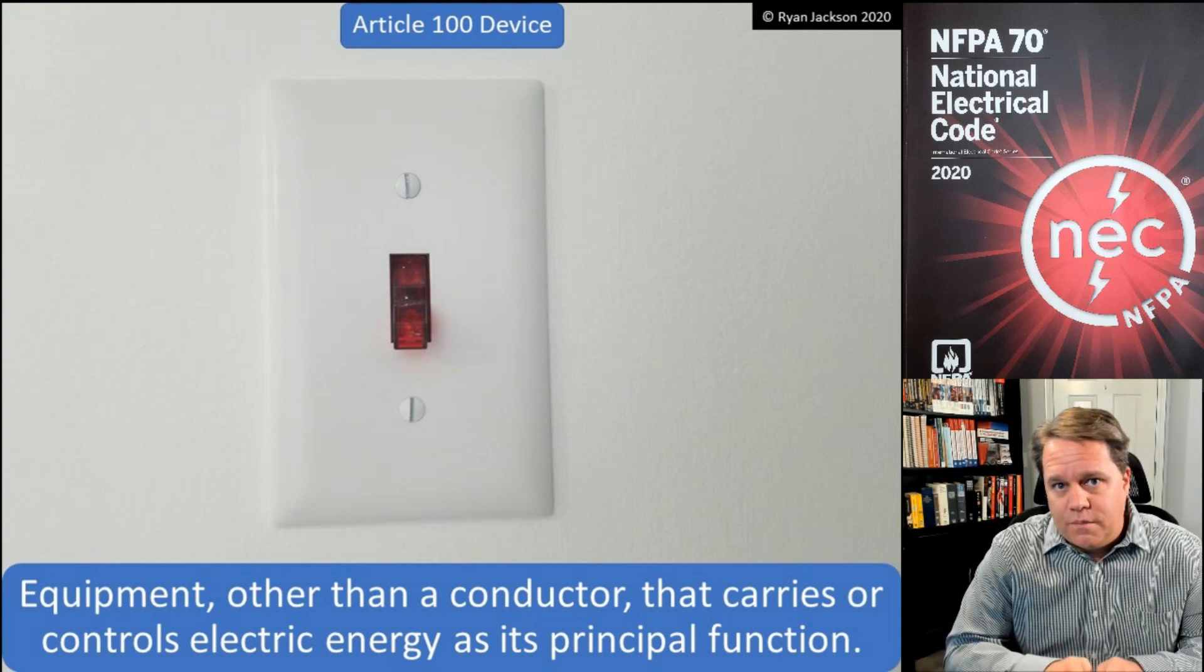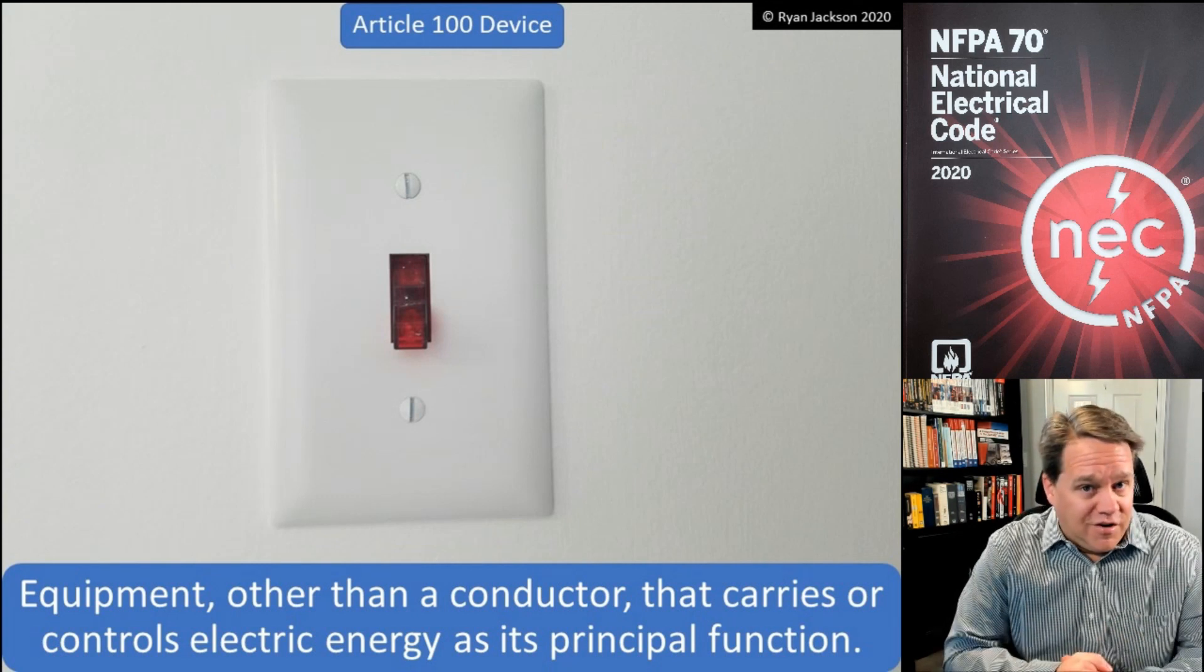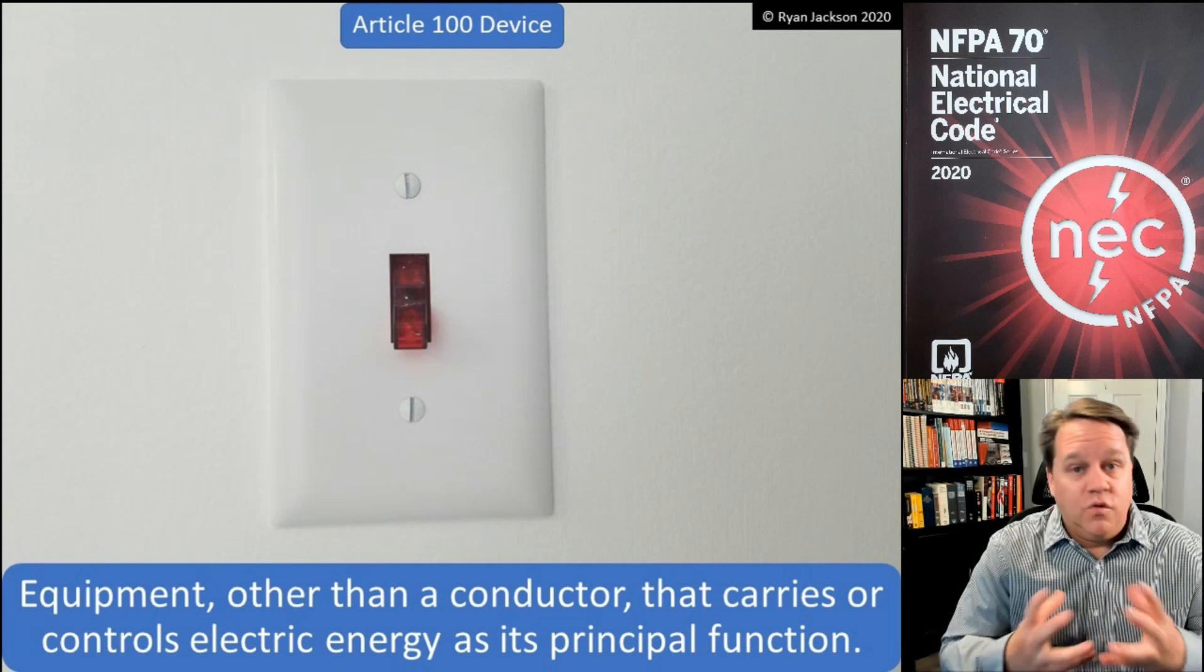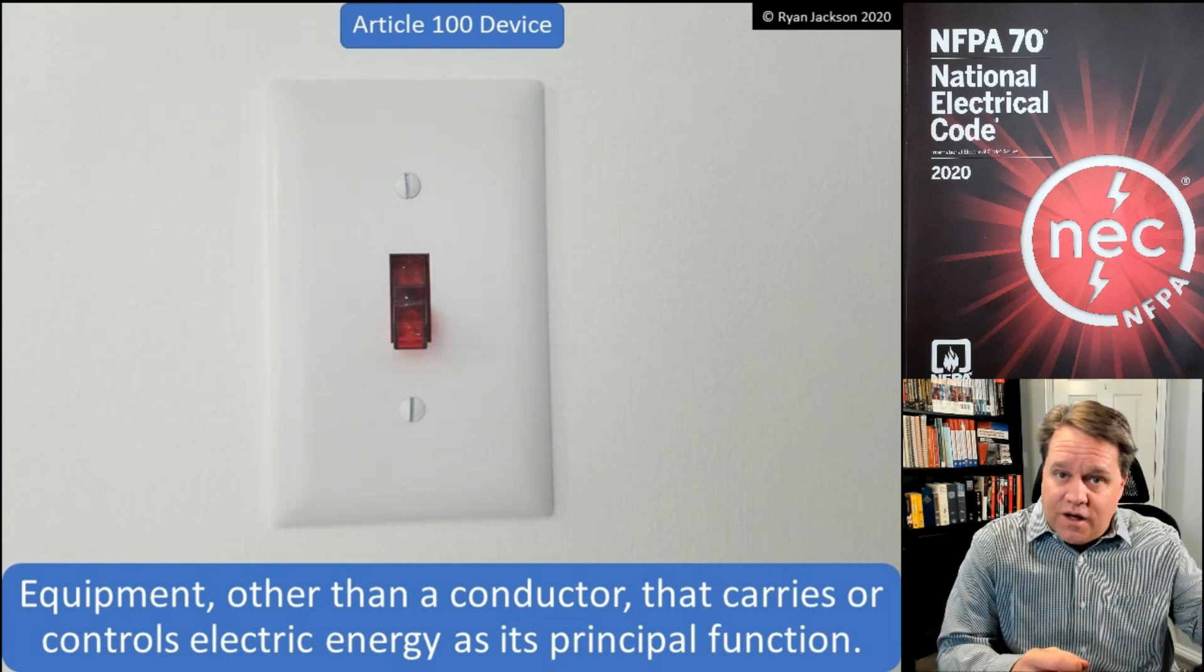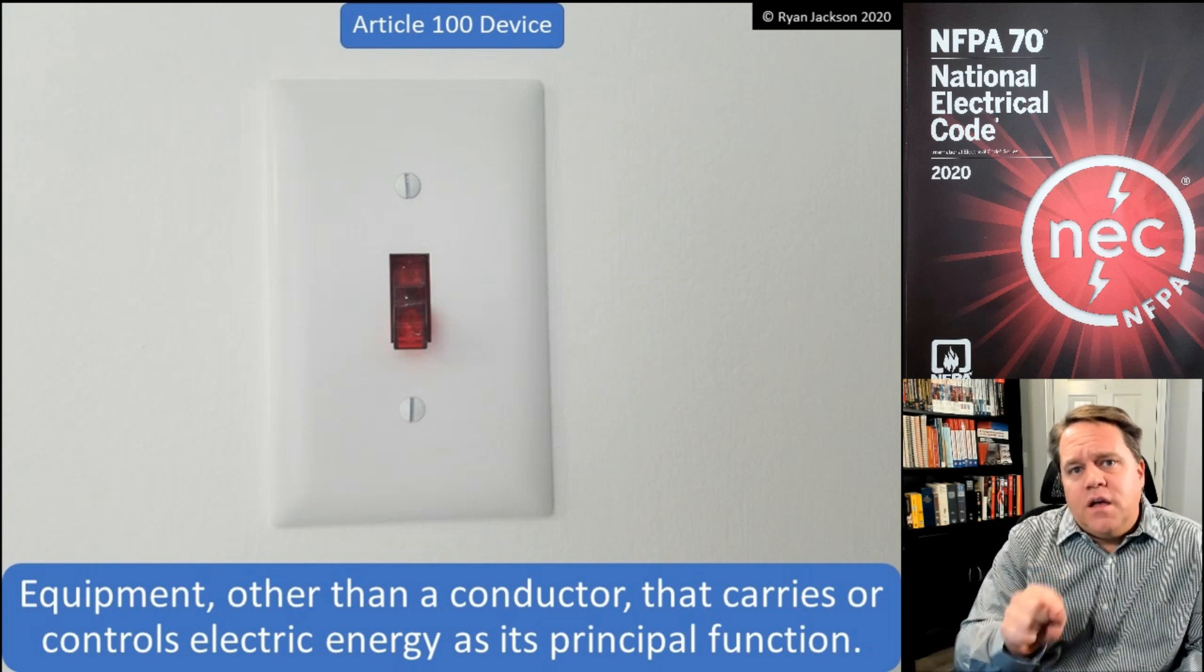So AFCIs used to be required just for receptacles in dwelling unit bedrooms, and then it said outlets in dwelling unit bedrooms. Okay, well an outlet is where we use electric energy. So you have lighting outlets, receptacles are installed at receptacle outlets.